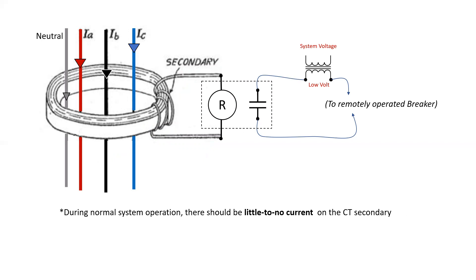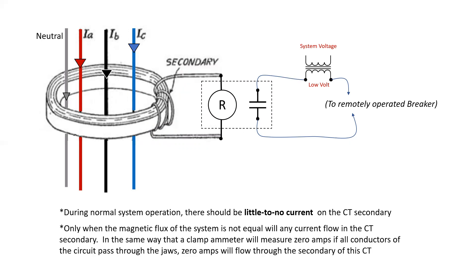During normal operation, there should be little to no current on the CT secondary. Only when the magnetic flux of the system is not equal or zero will any current flow in the CT secondary. In the same way that a clamp ammeter will measure zero amps when all the conductors of the circuit pass through the jaws, zero amps will flow through the secondary of the CT.